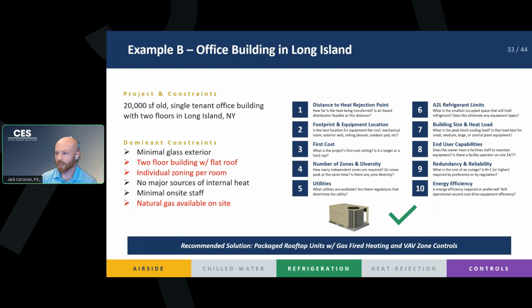And maybe in this case, since our rooftop units are flexible, we have individual zones. We use VAVs, right? Each office cluster or conference room gets its own VAV and its own thermostat, and every zone is going to be able to have its own temperature control. And we want to use gas-fired heat because they have natural gas at the site. So this is a pretty good application for packaged rooftop units. You've got your gas heat, you've got individual zones, VAV control, and you can stick everything on the roof, no problem.